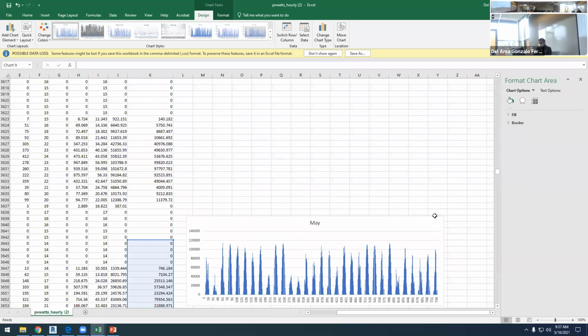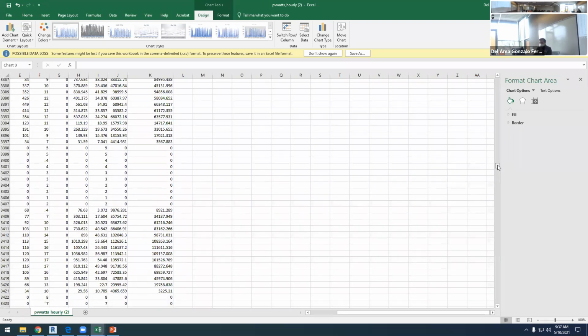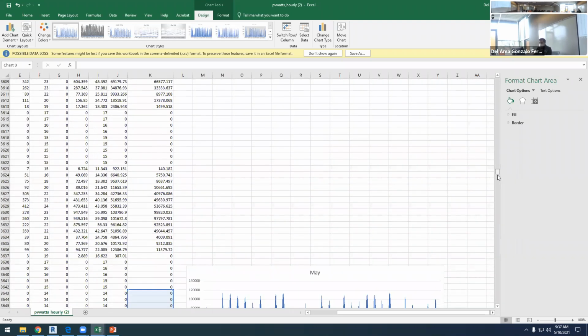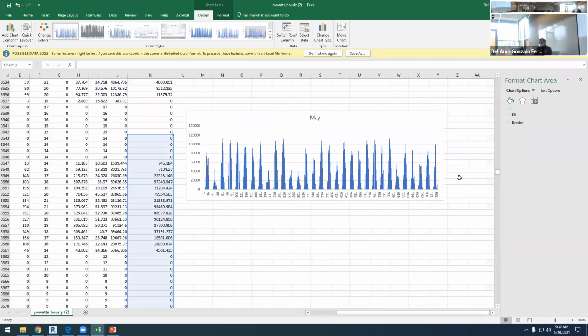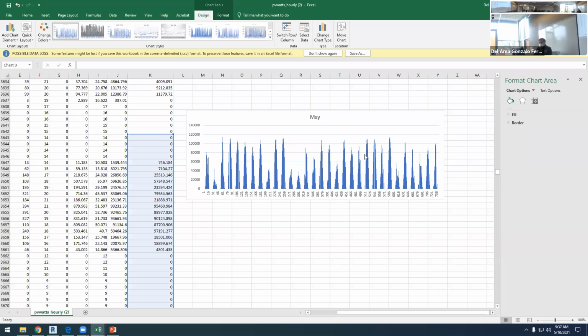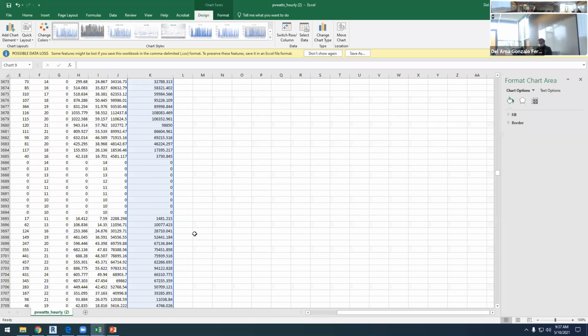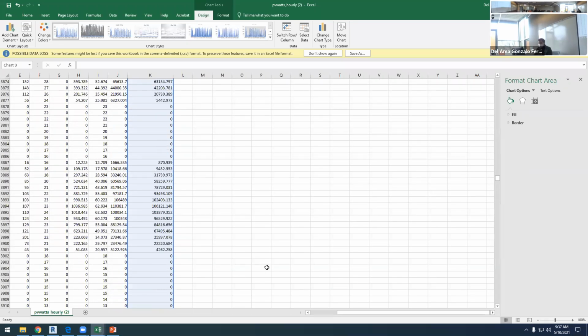Okay, so that's interesting. And it's not that, okay, we have good weather, hot summer, so we will produce more energy in summer than in winter. It's not always like this. So this technology is complicated because the amount of sun, the hours of sun, of course, matter, but the temperature of the cell matters as well. So in summer, we will have higher cell temperatures, and that will reduce the energy production.